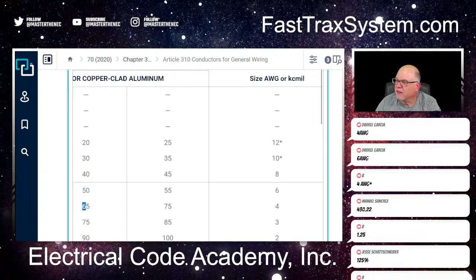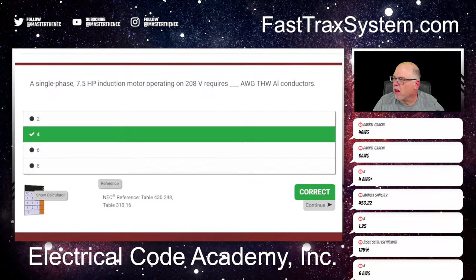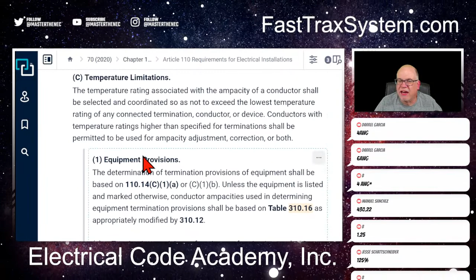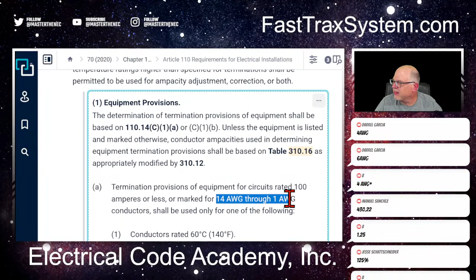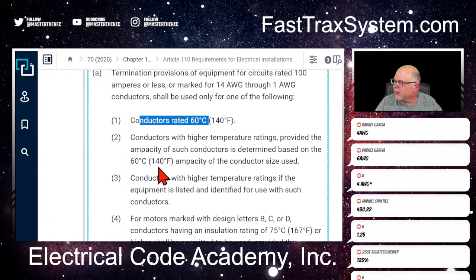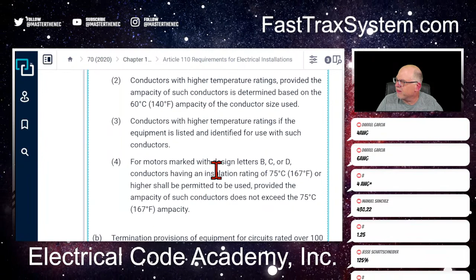They didn't even give you the 430.22 in here, but I gave it to you. So remember, motors can do things differently. If you're saying, where does it say that, Paul? Let me take you to the code so you're not confused about the 75 degrees C for motors in 110.14. Here's the provision for terminal limitations. It's 14 through 1, rated 100 amps or less. Typically it'd be 60 degree, but here you've got motors rated design B, C, and D. The default motor is B, and it tells you that you can use the 75.